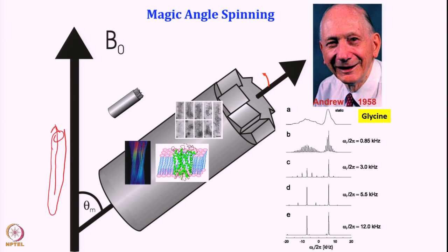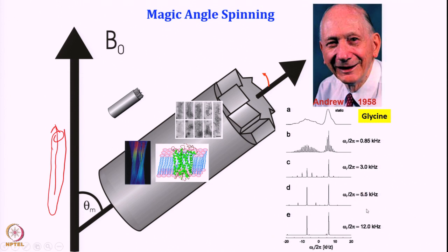12 kilohertz means 12,000 rotations per second — quite fast compared to an ultracentrifuge which does about 100,000 rpm, that is rotations per minute. Here we are talking about 12,000 rotations per second, which is very fast. The rotor material has to be really robust. These rotors are made of zirconium oxide, which is temperature-insensitive and can spin very fast. This is a moderate spinning speed; nowadays rotors can go up to 110 kilohertz, which requires a special arrangement.